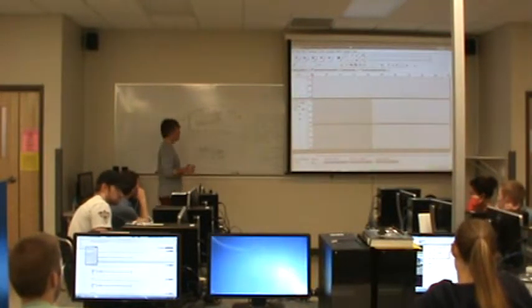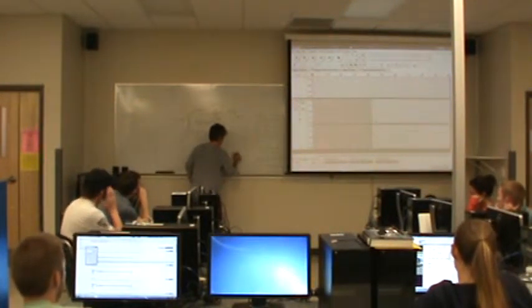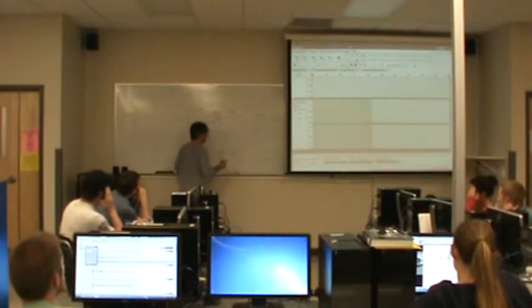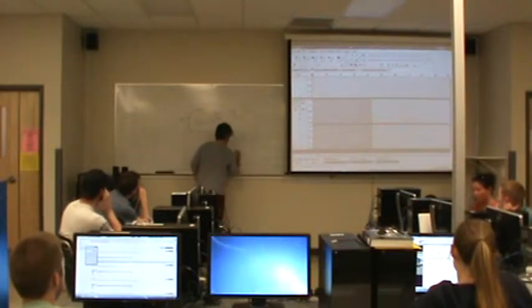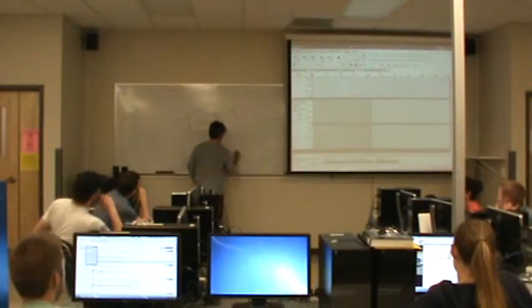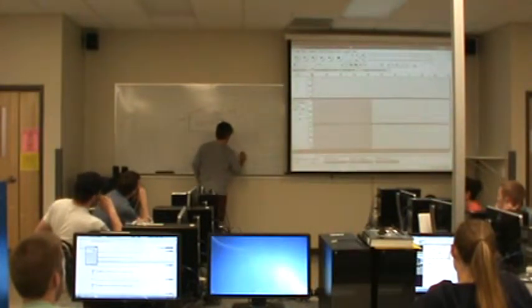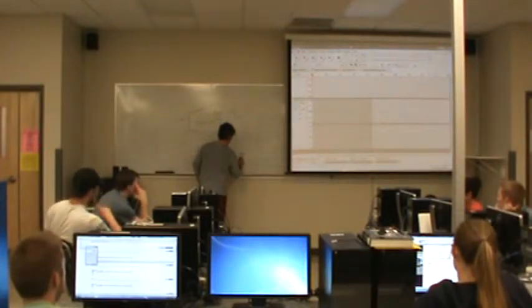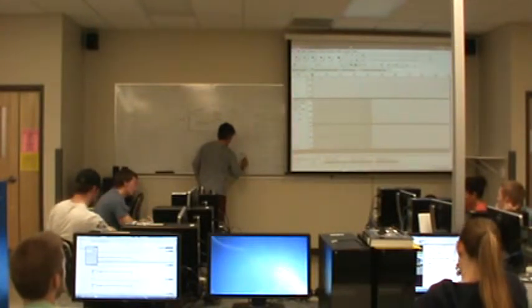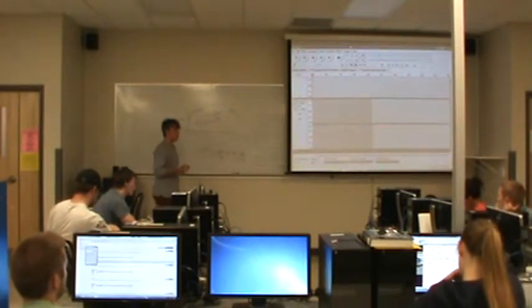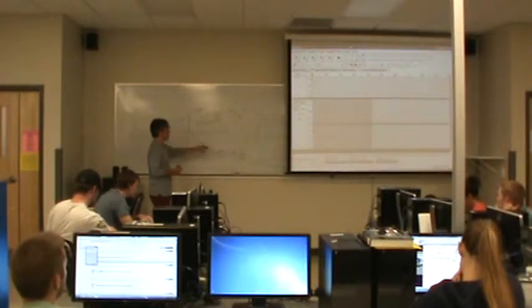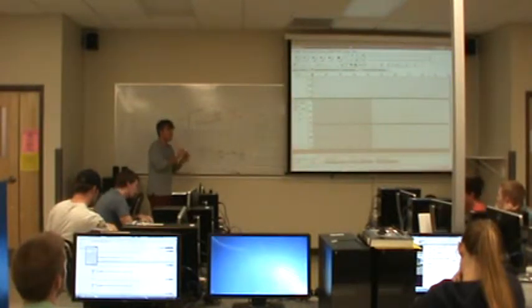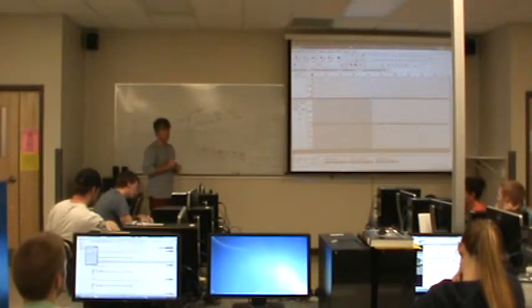How much? 390.6. So this is about 391 GPM per least significant bit. So the flow rate has to increase by 391 GPM before we detect that change. Does that make sense?